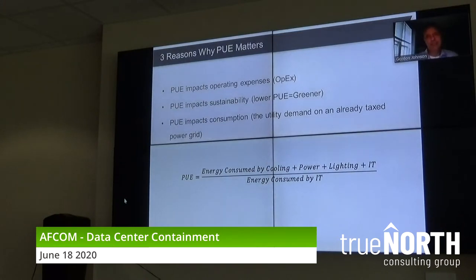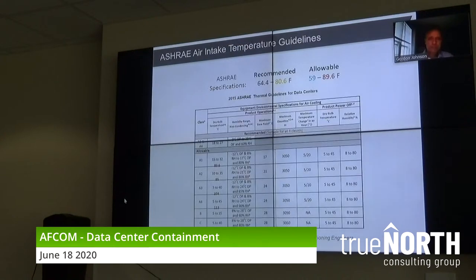I've seen, and I hate to say this, down in Texas, I think it was in the Dallas area, a PUE of 6.3, and at first I didn't believe the number they gave me. After doing a little more pre-research for a CFD, they were running their cooling units at 55. They had almost 7 times the amount of supply air versus the demand air, so yeah, they had a PUE of 6.3. But again, we want to get your PUE as low as possible.